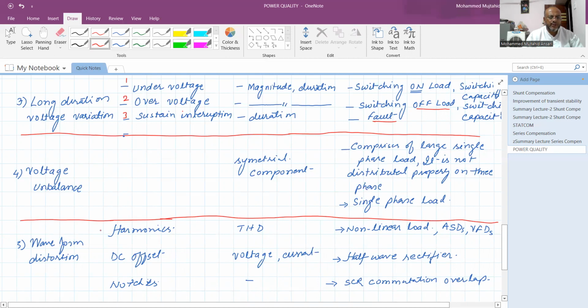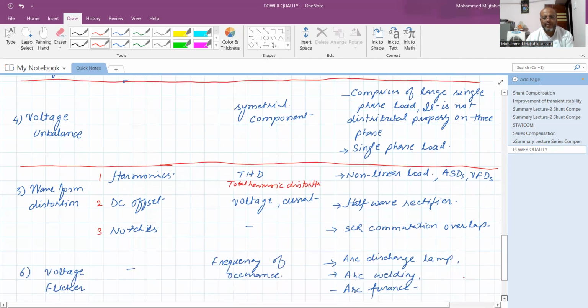Next is the waveform distortion. The waveform distortion is of three types. One is the harmonic, second is the DC offset, and third is the notches. Harmonic is characterized by THD, total harmonic distortion. It is due to the nonlinear load. It may be the SMPS which we are using in the computer, or it may be inverters or converters. It is due to the adjustable speed drive, where there are switching mechanisms, and variable frequency drives. DC offset is observed because of the half wave rectifier, whereas the notches are because of the SCR commutation overlap. And no doubt we are using the SCR in the VFDs and all these non-linear loads.